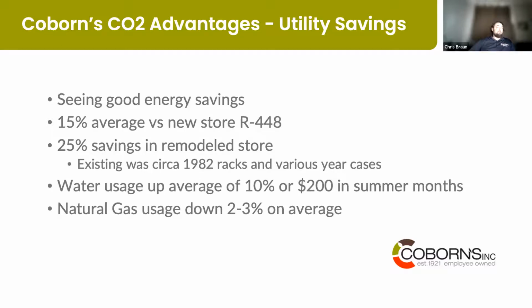In our remodeled store, which we went from, I believe it was 6 systems scattered throughout the store, some of them were built in 1982, with several updates here and there, we switched it to a new transcritical CO2 system with all new cases. We're seeing 25% energy utility savings in that store, and I'm probably being a bit conservative on that because we've only got 9 months worth of data on that store. We are seeing an increase in water usage due to the adiabatic gas coolers up there. It equates to about $200 a month. And we're seeing natural gas usage down about 2 to 3% across those 3 stores per square foot.